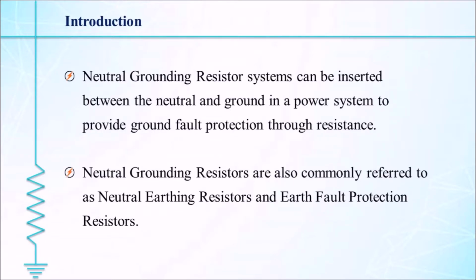Myself Onkar Veer. Let's start with the introduction to our topic. As we all know, the transformer is the heart of the electrical power system, so the protection of the transformer is a very essential part of it. And when it comes to protection and safety, the first term that comes to mind is the grounding of the device. NGR is the device used to serve this purpose. Neutral grounding resistor, as the name indicates itself, is a resistive device inserted between the neutral of the transformer and the grounding terminal. It is used for suppressing heavy fault current by dissipating it into the resistor. It is also called a neutral earthing resistor or earth fault protection resistor. Further, we are going to have detailed information about it.